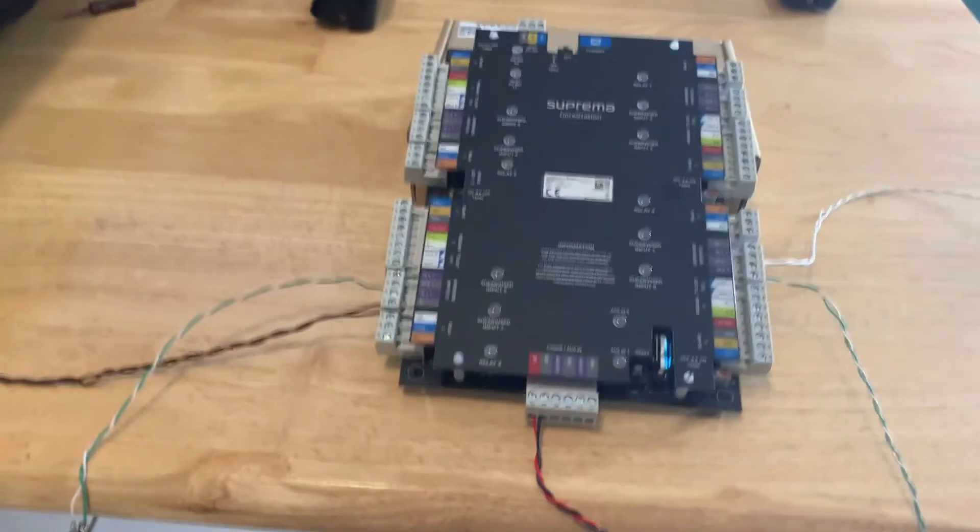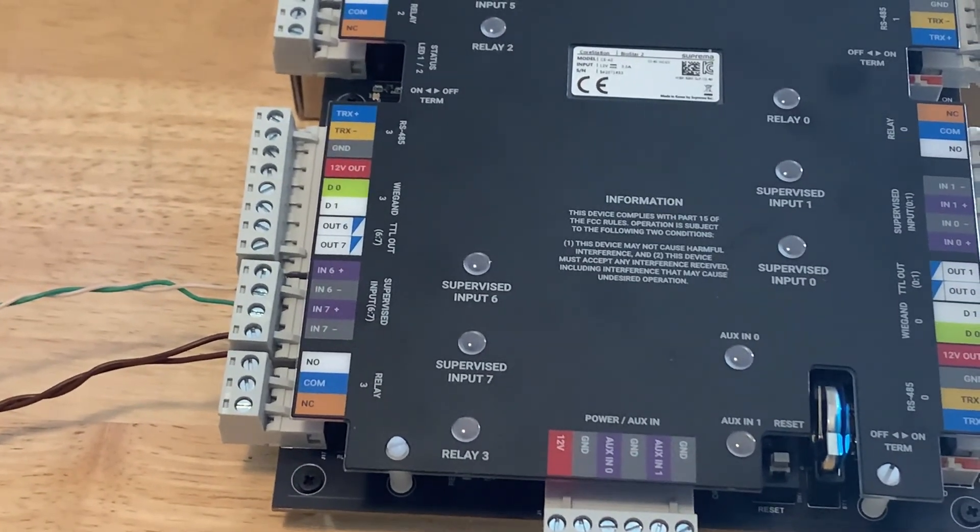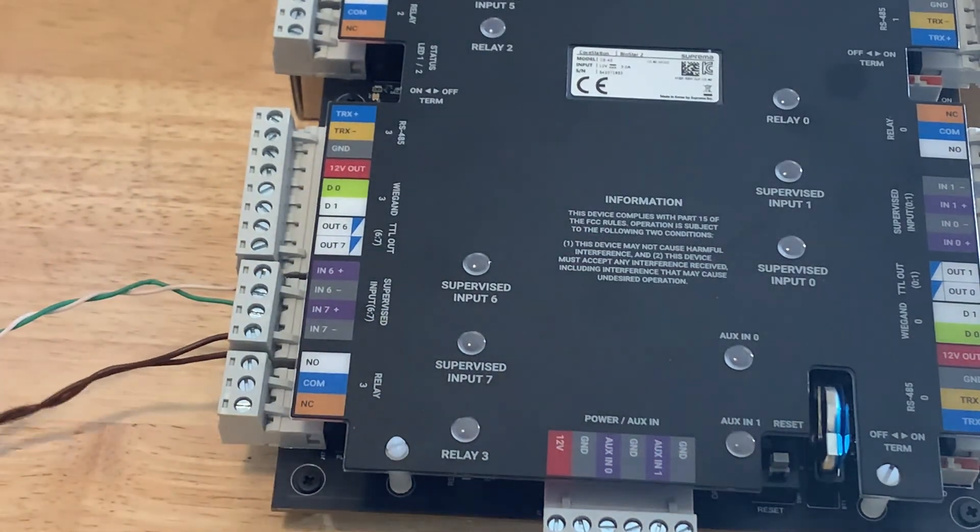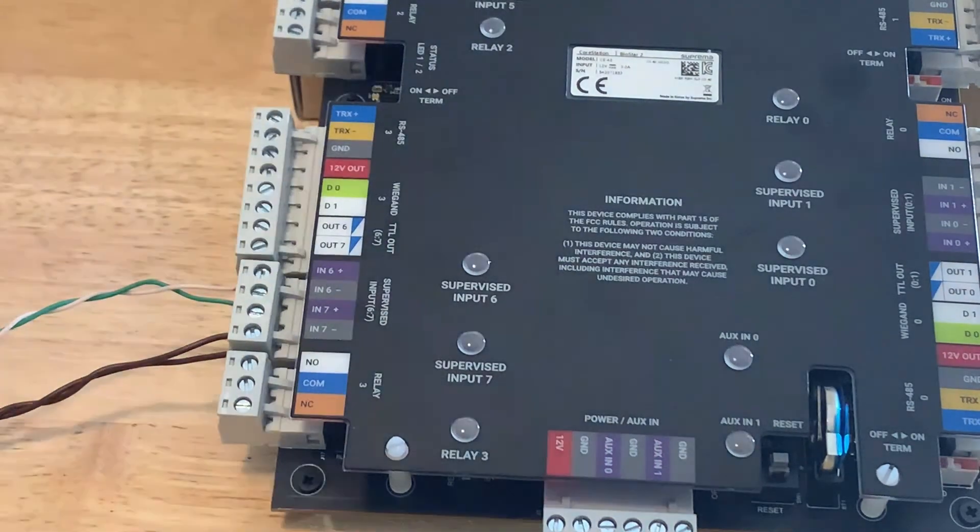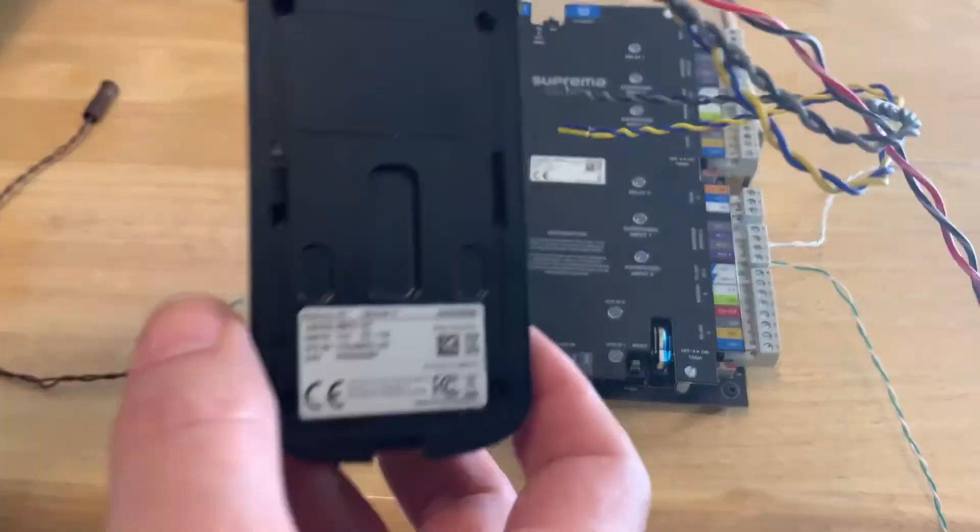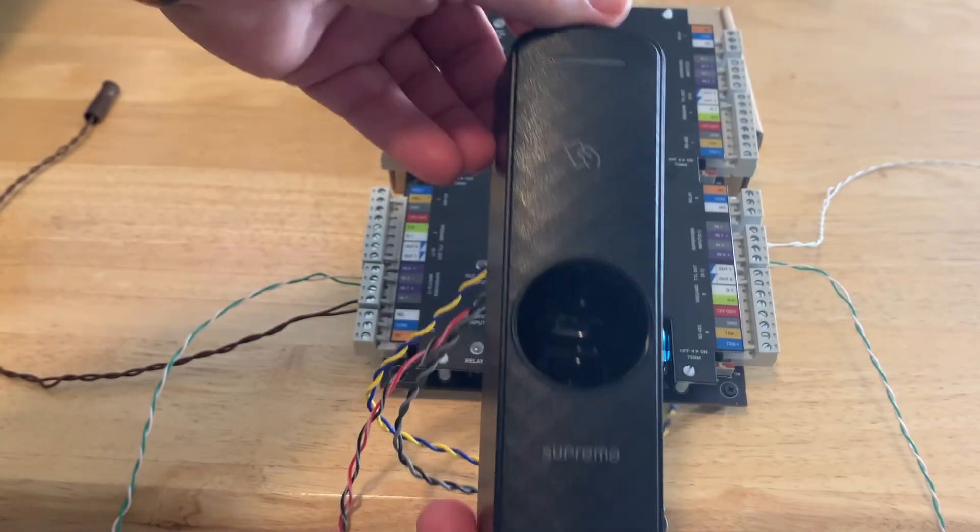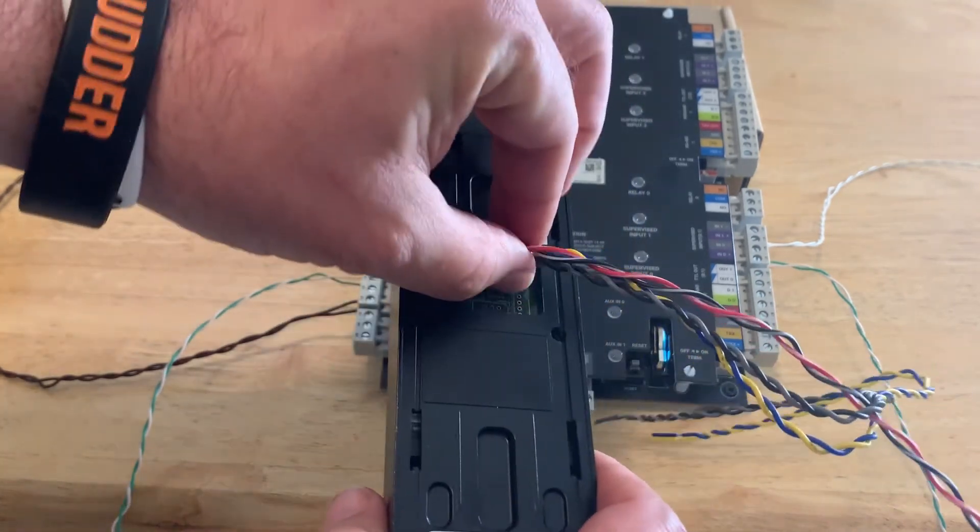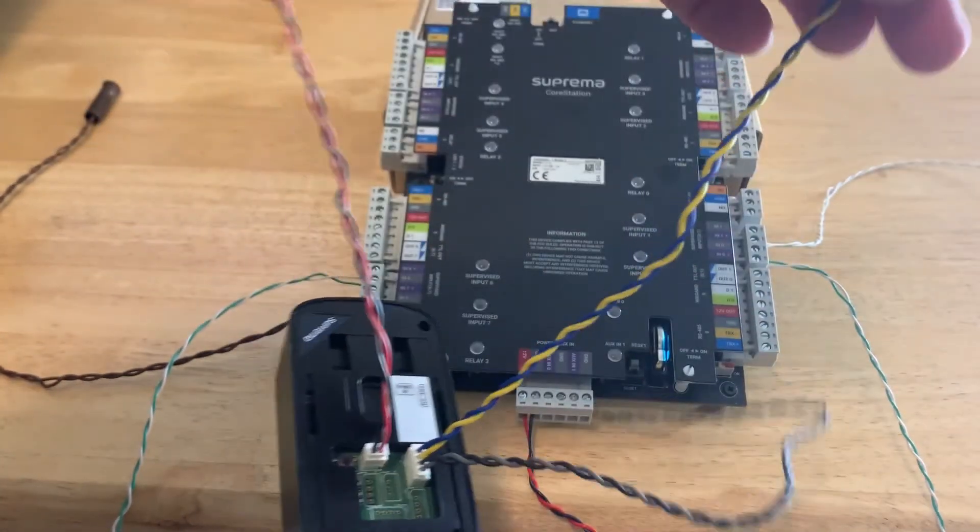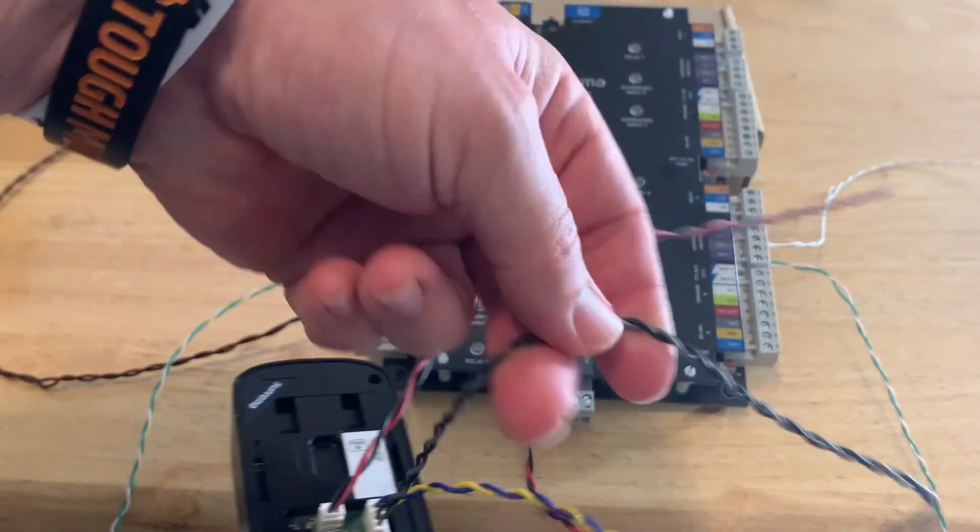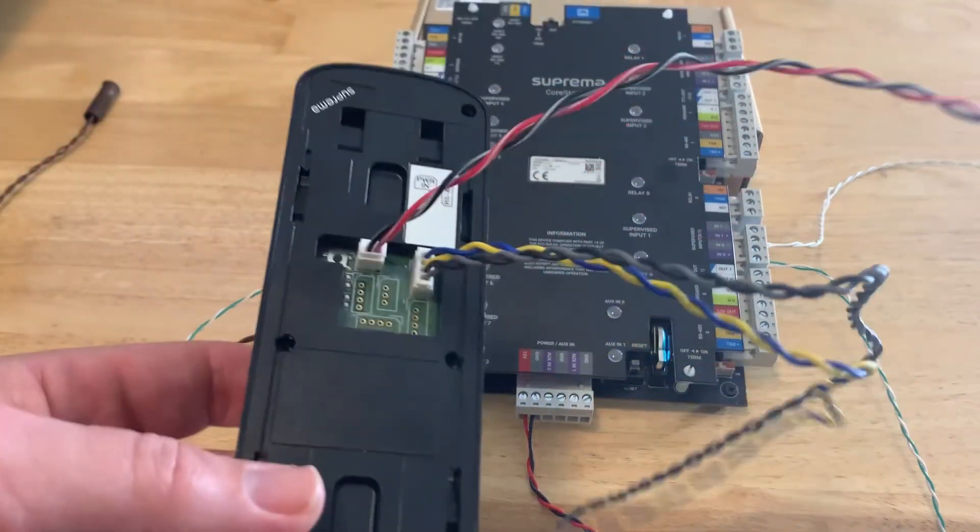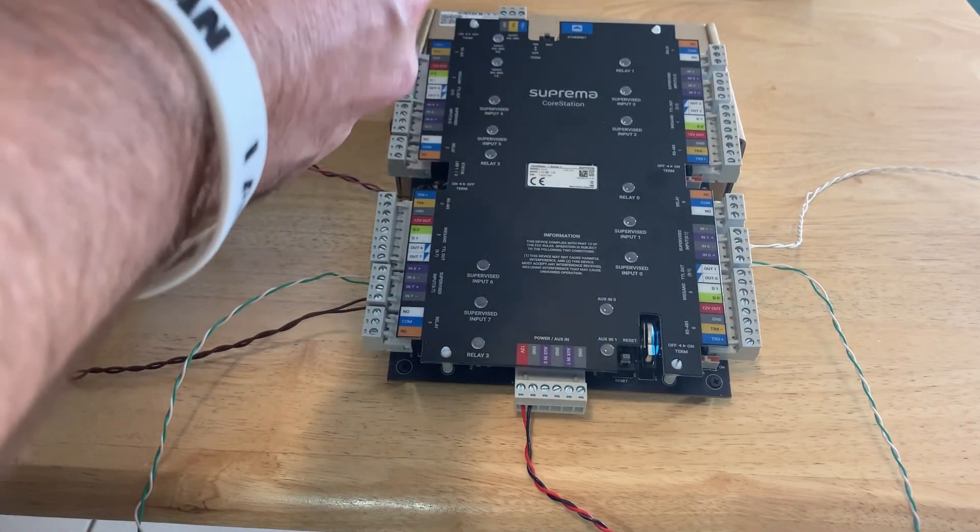All right so zoom in here on door port three as I've already went ahead and wired in a rex button and a door contact as well. Now when you wire up the R2 let me just go over that real quick with you. The R2, the BioEntry R2 is a fingerprint reader to present your finger here and card reader up here. This is the power connection 12 volt and then like I said we'll use the 485 connection and then the gray and black are 485 ground and shield in this application.